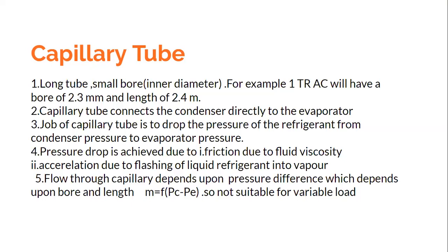Obviously, we can have a number of combinations of the bore and length. So I can change the length and accordingly the bore changes. The objective is to see that there is a reasonable pressure drop between the condenser and the evaporator. That is how the capillary tube is designed.